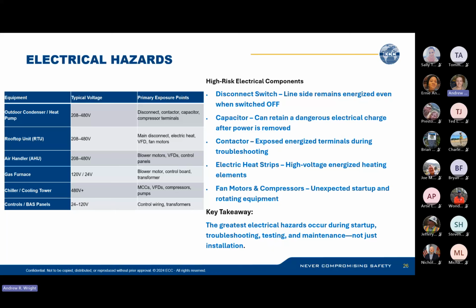Some high-risk electrical components are going to be your disconnect switches. Those are the levers that you'll see pretty close to where the HVAC systems are. Capacitors can retain a dangerous electrical charge even after power is removed. Contactors, that's where you have exposed electrical terminals. This is where your HVAC techs are going to want to open up a system and troubleshoot it. It has to be on, so you want to make sure they're wearing their proper PPE, like arc flash PPE. If they have to work on energized systems, there are actually energized work permits if you have to work on live panels.